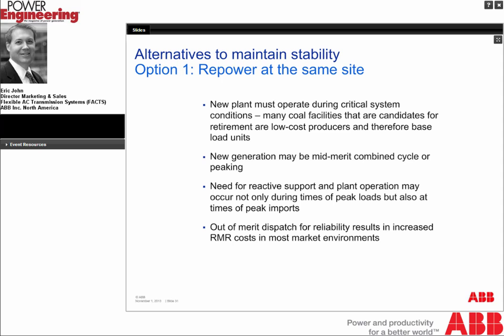The new generation that gets sited on this location could very well be some kind of mid-merit combined cycle or a peaking unit, probably running on natural gas, based on the economics that Rodney had shown. And the unit might not be dispatched when it's needed for grid stability. And so this can set up a catch-22 situation, because the need for reactive support might not correlate to when the plant is operated, because often the time when reactive support is needed is during a time of peak imports. And by definition, your peaking unit or your mid-merit unit aren't necessarily going to be dispatched at a time of peak import, which could very well be when the system is most vulnerable from a reactive point of view, because again, the VARs are so highly dependent on the location.